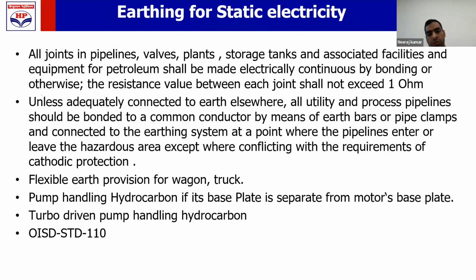Static electricity is another source of ignition for the hydrocarbon industry. To prevent or control that static electricity, following are the requirements. All the pipes, valves, and storage tanks shall be made electrically continuous by providing bonding or by keeping the resistance at the joints less than 1 ohm. So many times you might have seen that some bonding conductor is provided on the joints in the pipe. Sometimes it is not provided. Both are okay, provided you are able to maintain resistance less than 1 ohm.